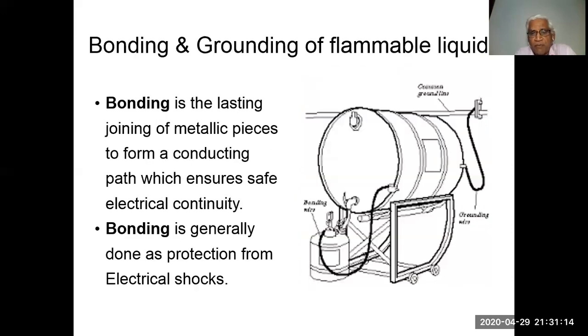Bonding and grounding of flammable liquids. See the figure given on the right side. Bonding is the lasting joining of metallic pieces to form a conducting path which ensures safe electrical continuity. Bonding is generally done as protection from electrical shocks. In this particular figure, you can notice that the metallic pipe has been connected to the container into which we are transferring the liquid. So these two are at the same potential, and there is no chance of a fire at the point where the transfer is taking place.